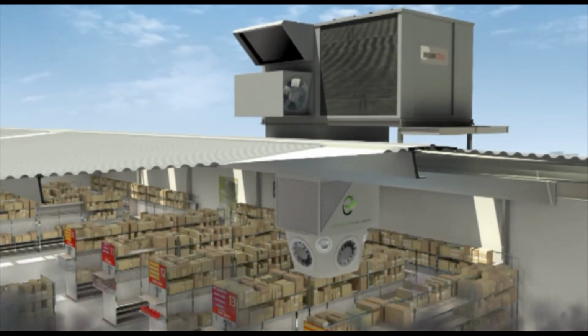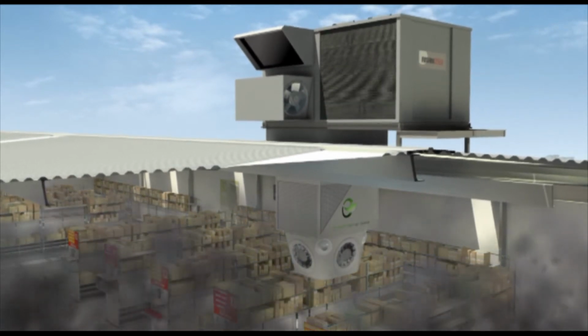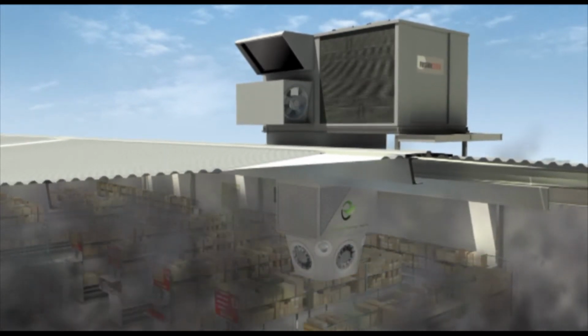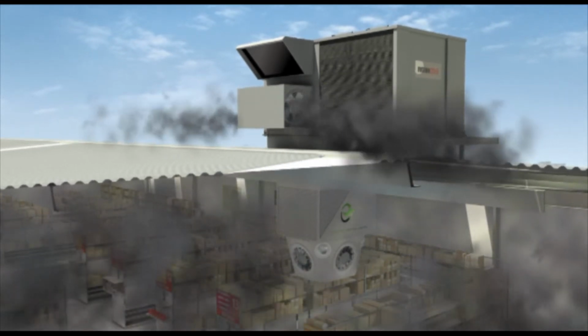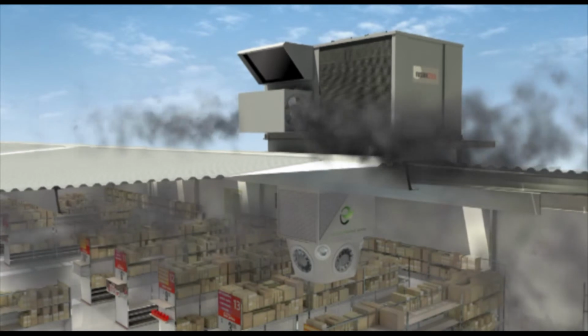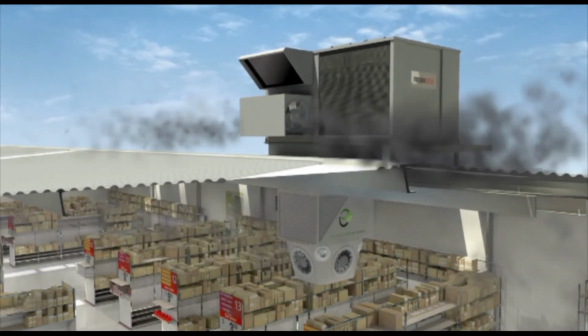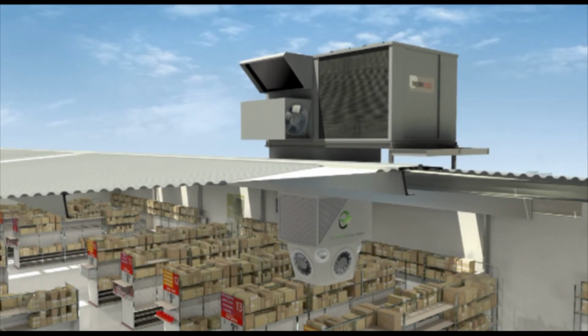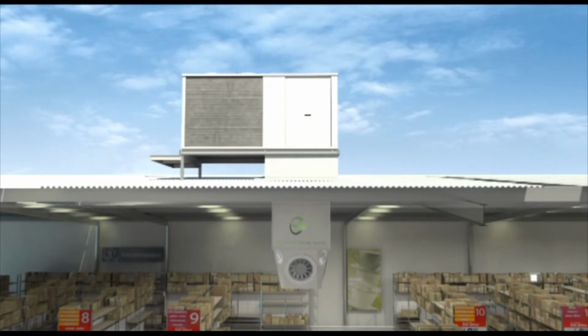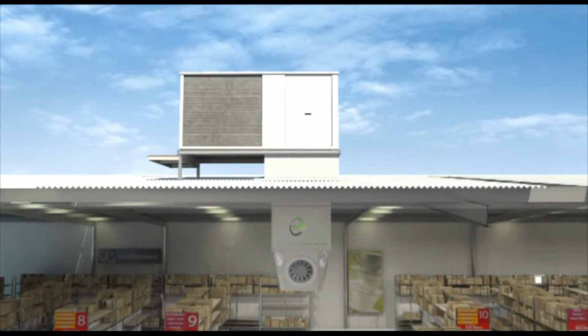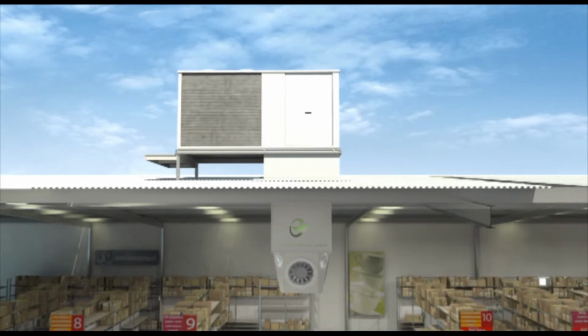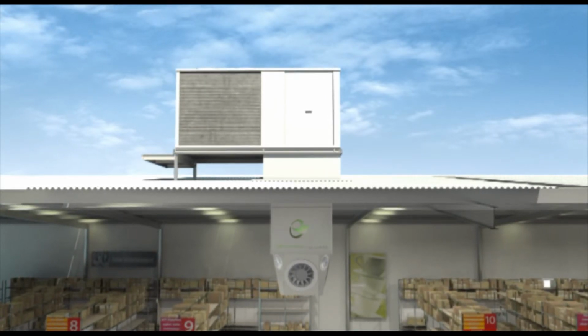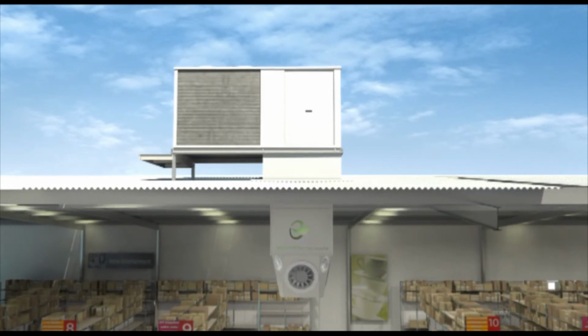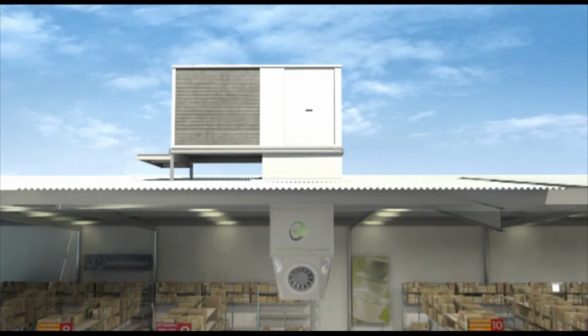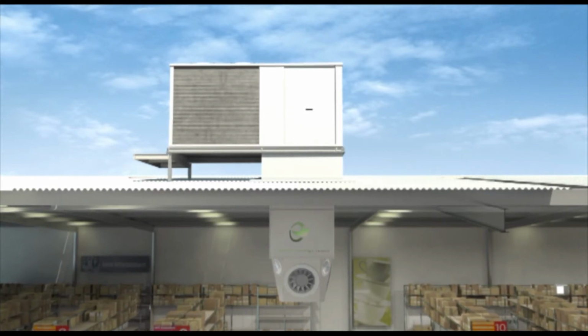Note the smoke exhaust fans on the side of the rooftop package unit. These fans serve as both pressure relief during normal operation and smoke spill in fire mode. Using this physical configuration, smoke is exhausted by the return air section of the module, which saves an additional and separate roof penetration for a smoke exhaust fan. There is minimal galvanized structure above the roofline, saving substantially on capital costs. A specially designed overflashing fully protects the ductwork from the elements and eliminates the threat of water leaks even in tropical downpours.